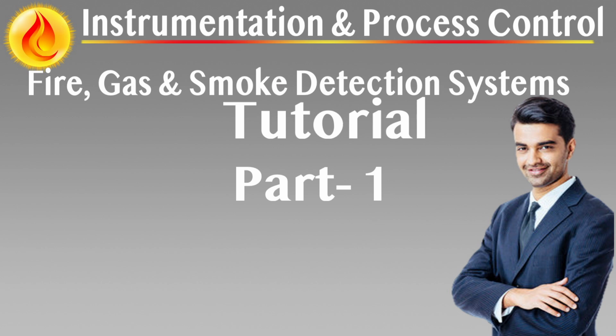System alignment and lifecycle support. The integration of detectors into FGS systems demands compliance with clear architectural and hardware guidelines. Detectors must support hardwired analog 0 to 20 milliamps or potential-free contact interfaces, diagnostic signaling for faults like beam blockage, fouled optics, or sensor aging, field replaceable sensors, and simple one-person calibration procedures. System integrity is enhanced when detectors are aligned with HMI design, providing meaningful feedback through both mimic panels and DCS interfaces. Color-coded annunciation, voting feedback, and zone-wise isolation all support rapid decision-making.